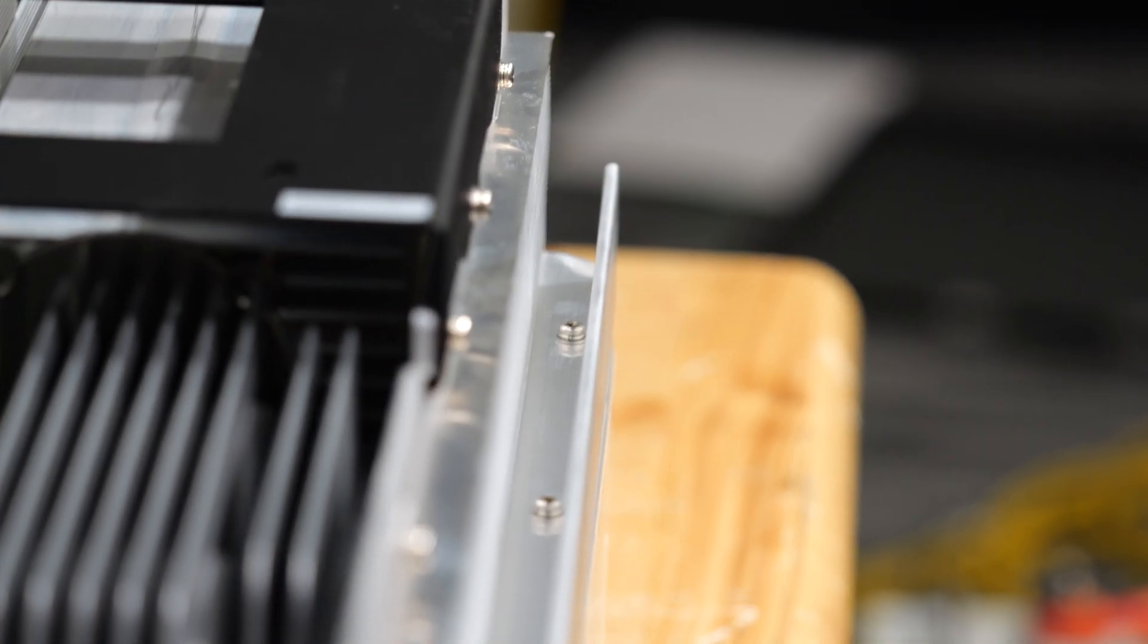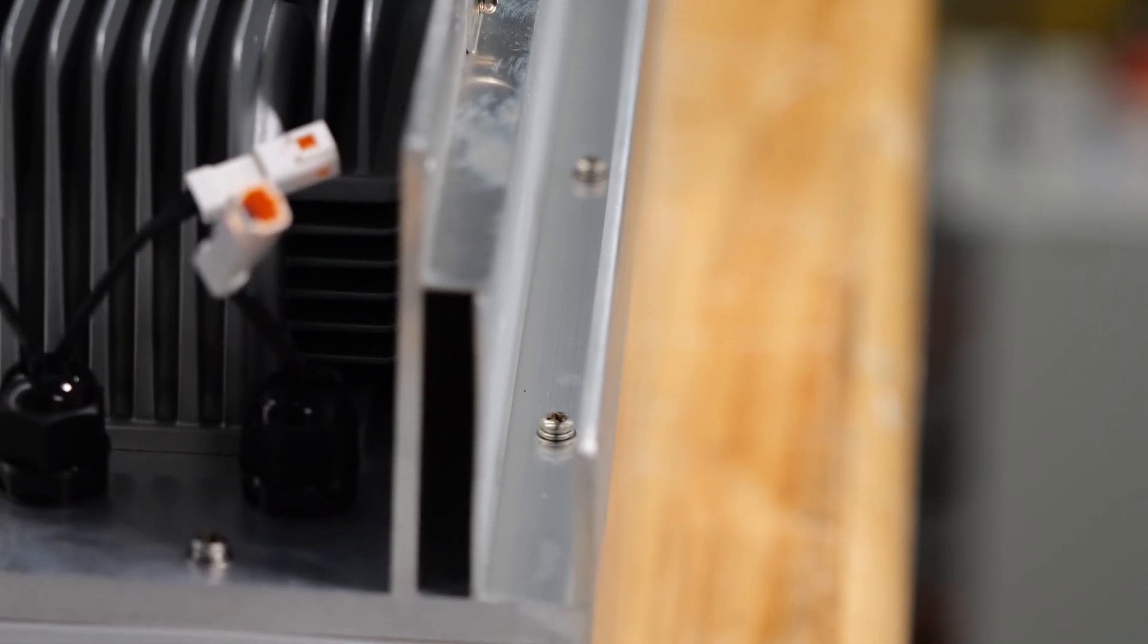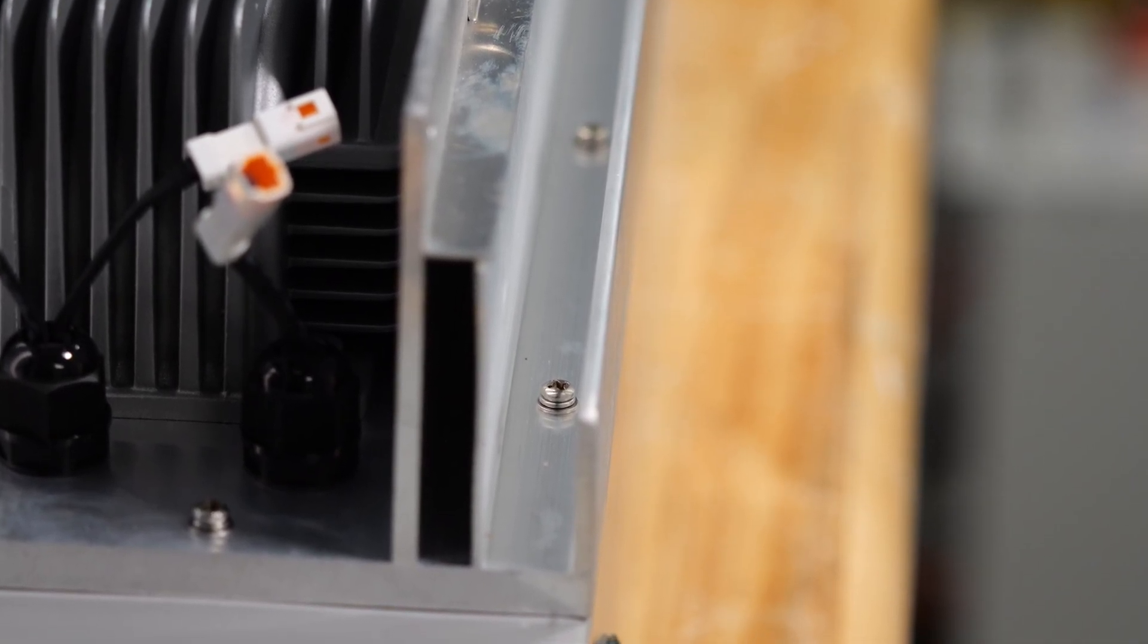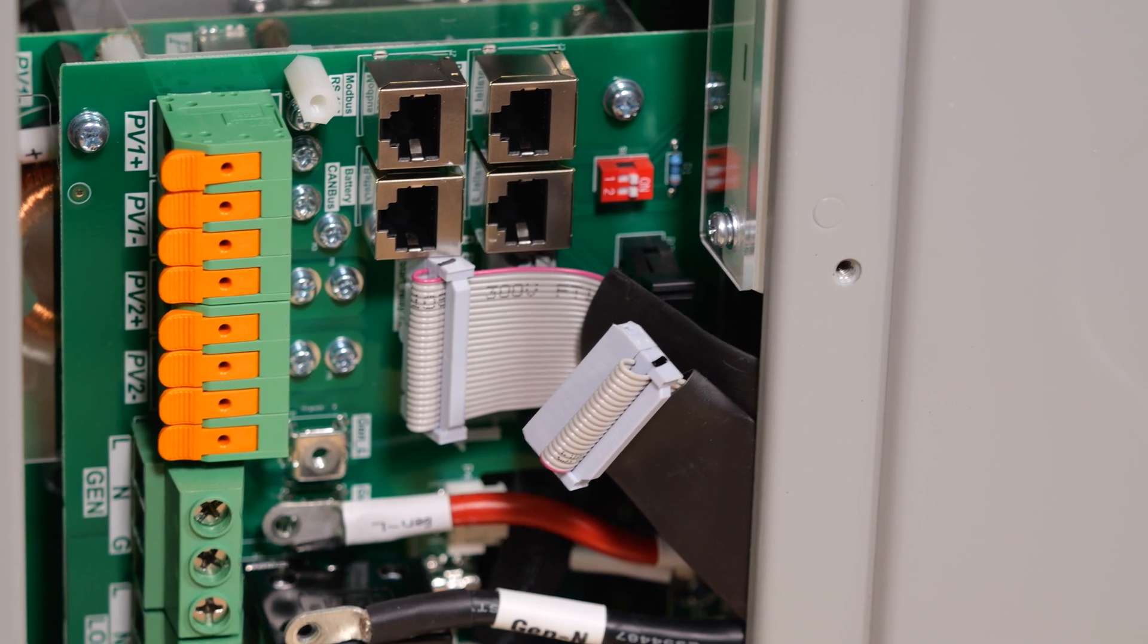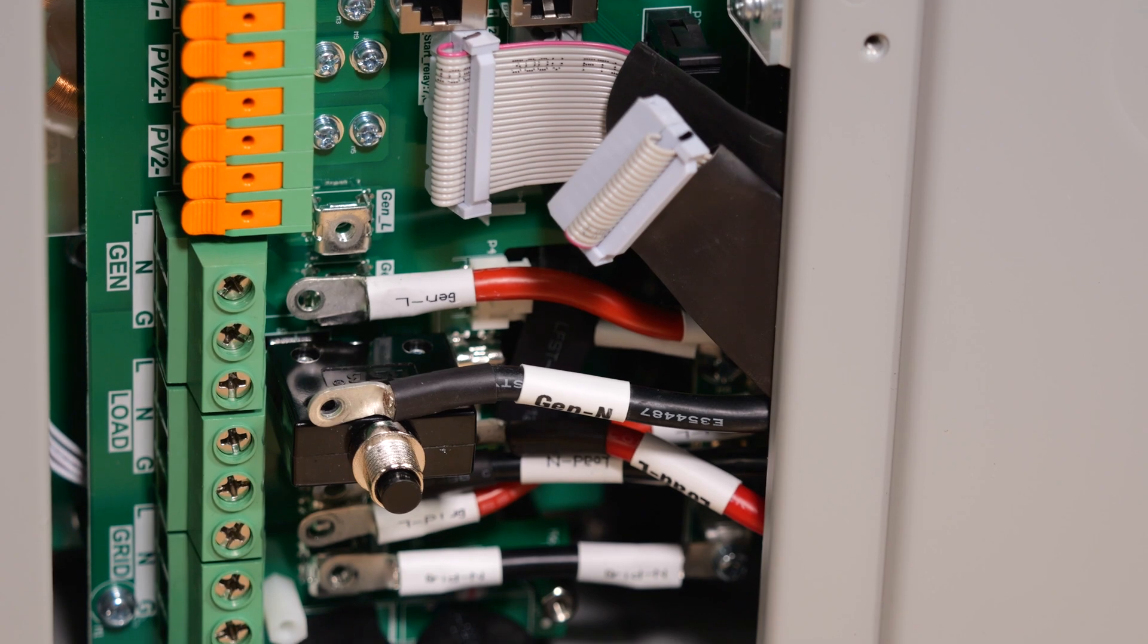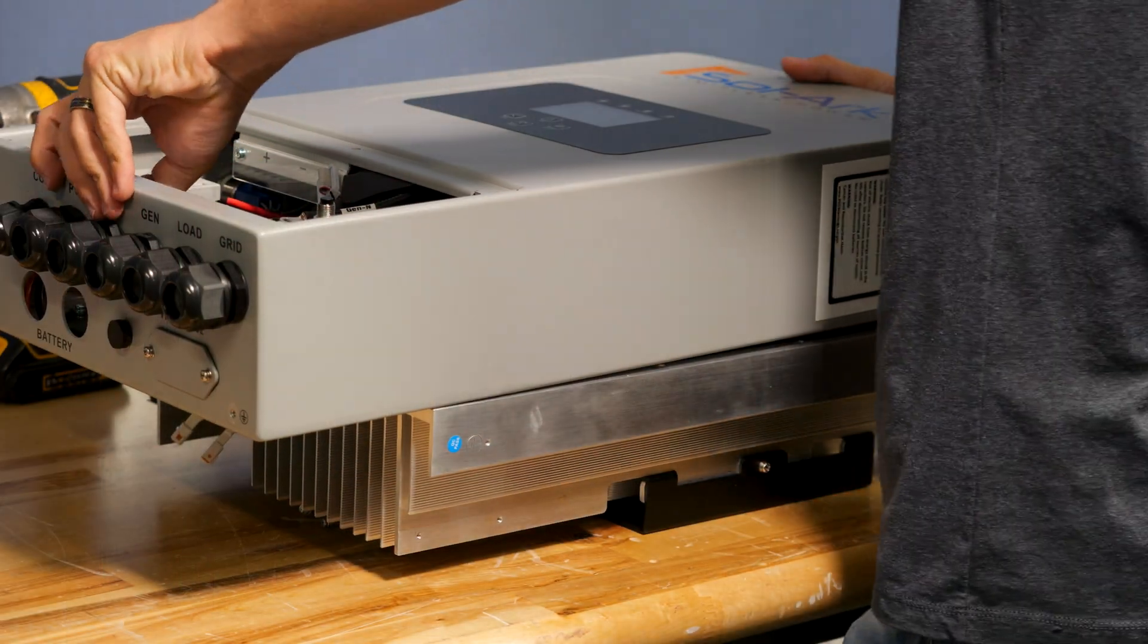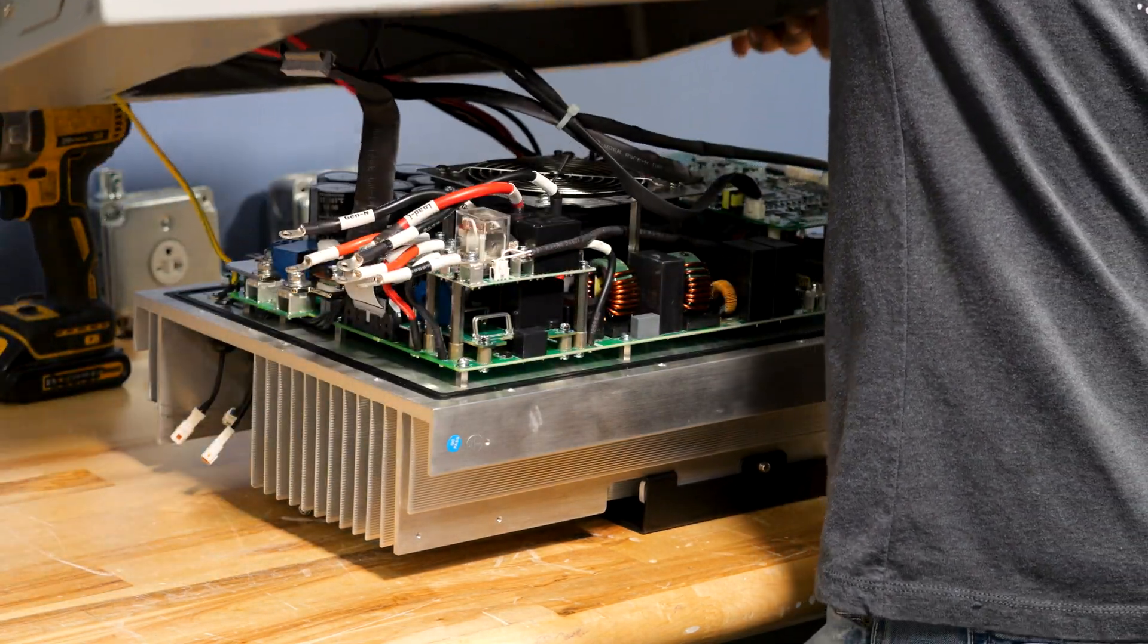There are screws down either side of the inverter that remove with a Phillips tip screwdriver. They're pretty easy to take out and they have lock washers and flat washers on them so they're not going to vibrate out on accident. Two ribbon cables are unplugged and six electrical wires are unscrewed from the circuit board in the wiring compartment. And then the front part of the inverter simply lifts up and slides over.